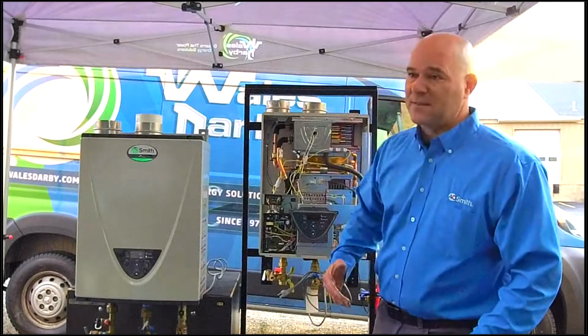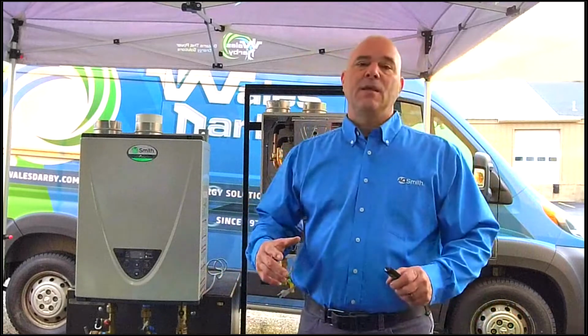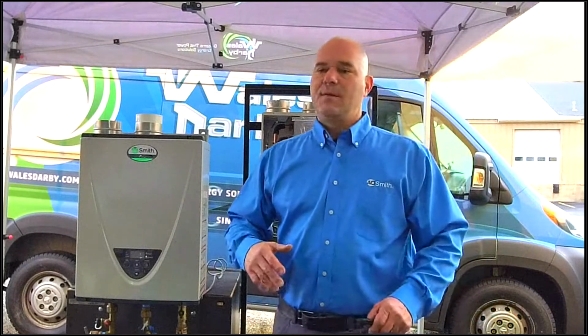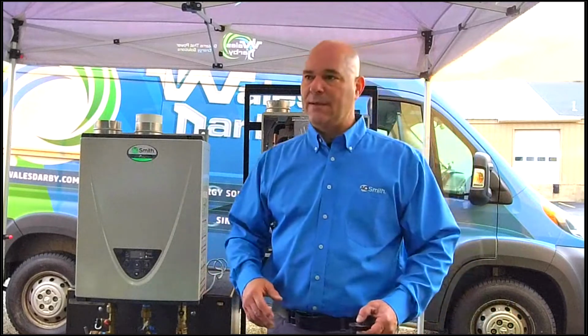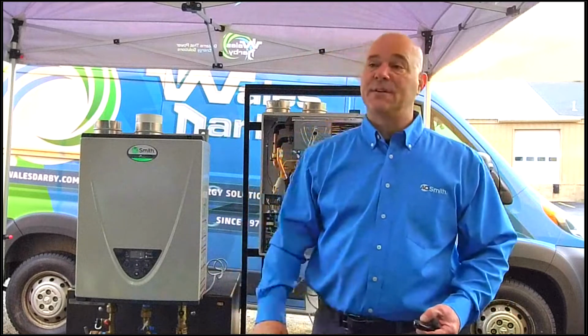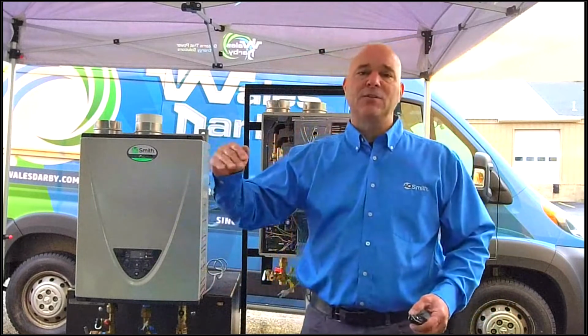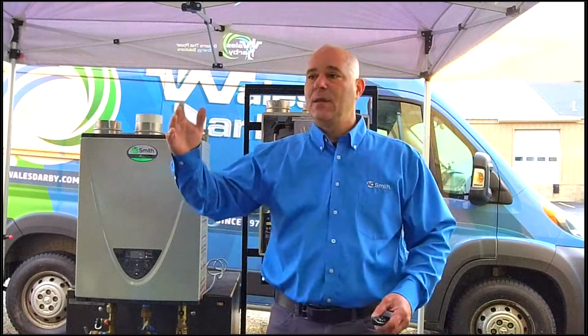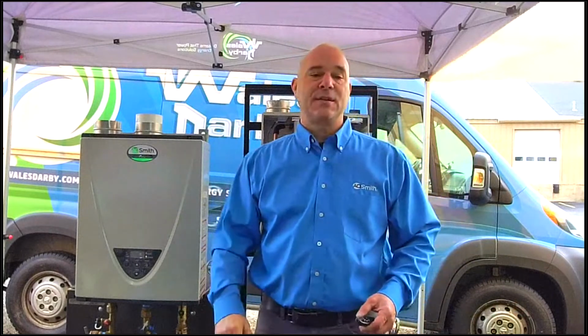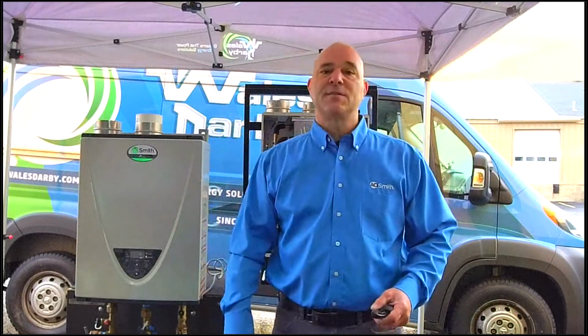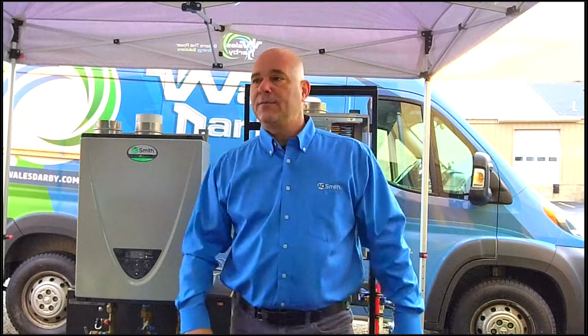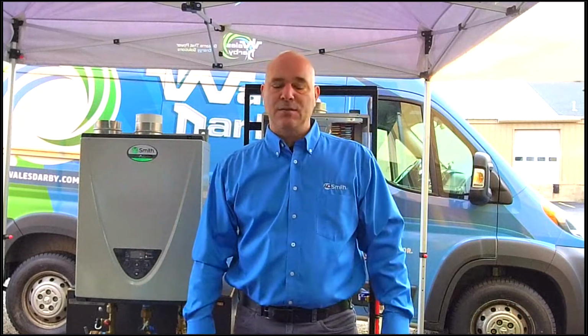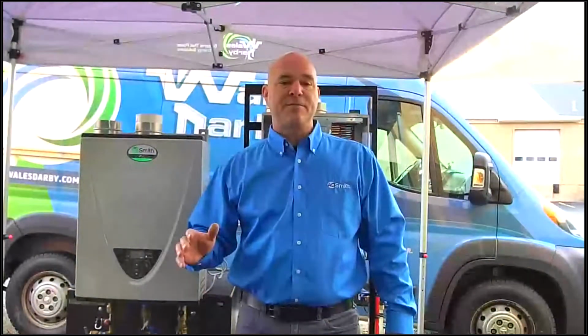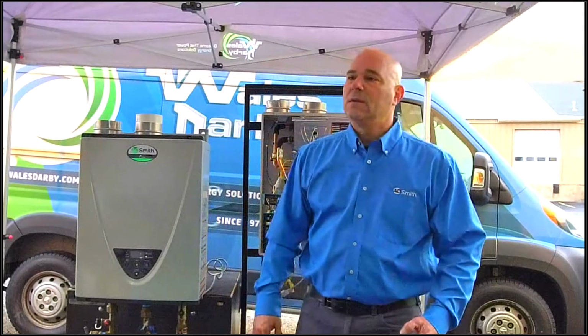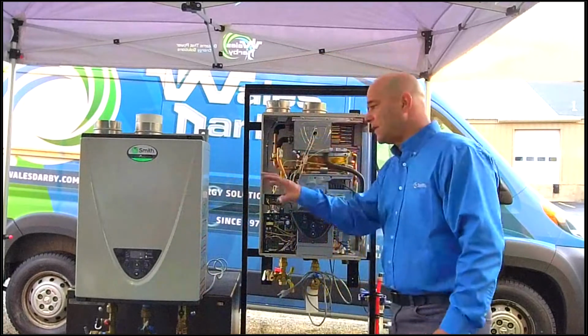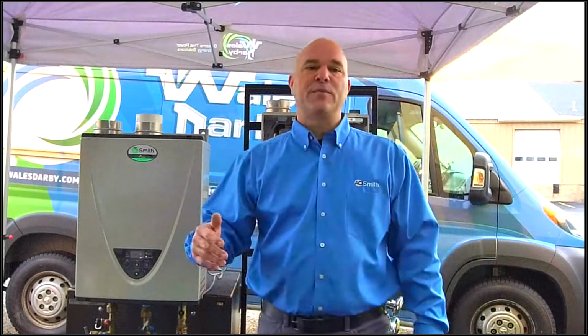Flow rates on these, basically, if we're talking a small condominium, one person, maybe two people, not a lot of hot water use, you can get away with the 140. That'll get us about 3.1 gallons a minute at a 70-degree rise. If we step up and go to the 240, that's the 160,000 BTU unit, that's going to get us about 4.2, 4.3 gallons of hot water per minute at a 70-degree rise. And if we step up to the next level, which is the 180,000 BTU unit, that's going to get us up in that 5.0 range. And if we get all the way up to the 199s, the version that we're looking at here, that's going to get us up into that 5.4 range.